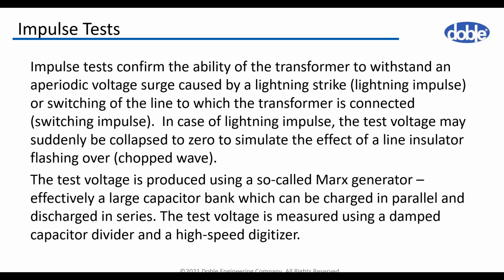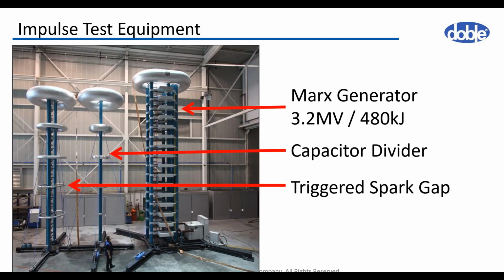The review of the dielectric tests will start with impulse tests. Their purpose is to verify the capability of the transformer to withstand aperiodic surges associated with lightning strikes and switching operations in service. In addition to lightning impulse, the test voltage may be suddenly collapsed to zero, simulating insulation flashover, and to check the capability to withstand high frequency phenomena. The equipment used for the test consists of an impulse generator, which charges in parallel and discharges in series to produce the test voltage, a capacitive divider for measurement of the test voltage, and a sphere gap, which is responsible for chopping of the lightning impulse.